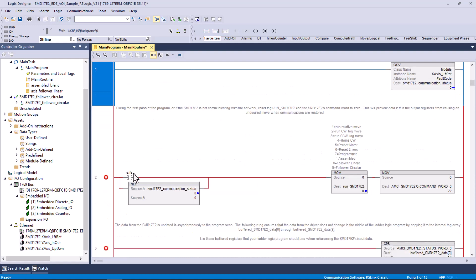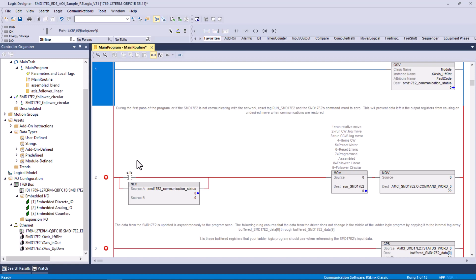This is basically a status bit. It's FS for first scan bit, and in the older, I don't remember the exact memory location, but anyway, this is the first scan bit. This is used for housekeeping, this rung. This bit will only be true for one program scan at the first scan. You go from program to run, or you go into the run mode. On the very first scan, this will go true, and it will perform these functions.